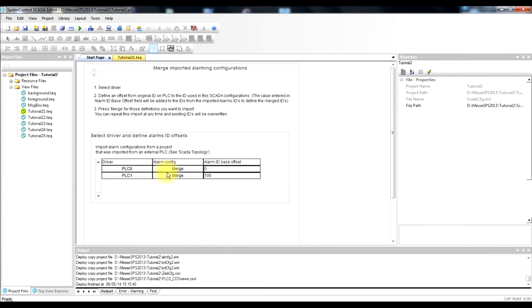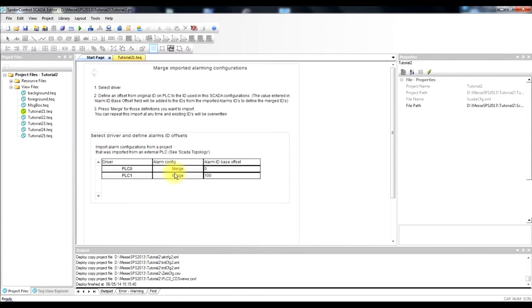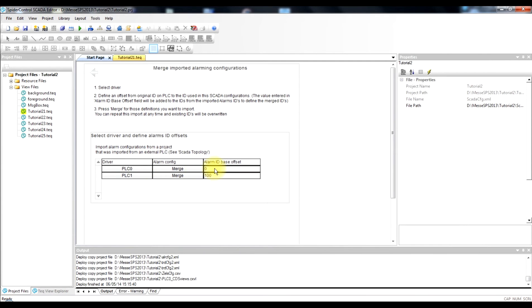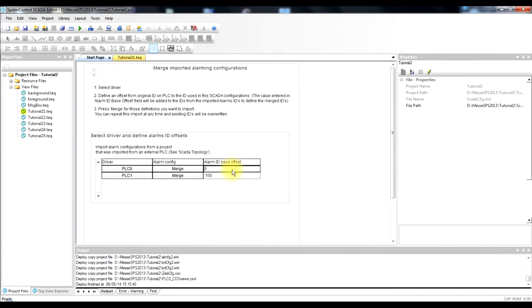Now the revolution in alarm configuration is our alarm harvesting. This overview shows that from both PLCs we were able to find and import alarm configurations. And we can now define an alarm ID offset to the alarm IDs that came from the PLC. From the PLC, the alarm IDs usually begin with 1. And because we have several PLCs we can define an offset in order to have a continuous alarm ID space.